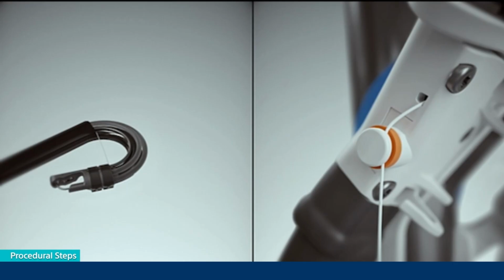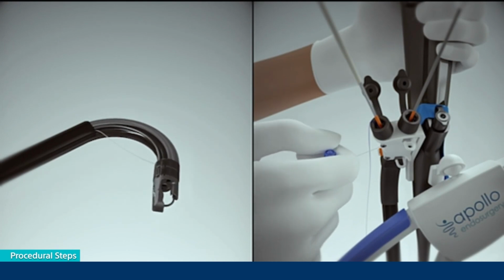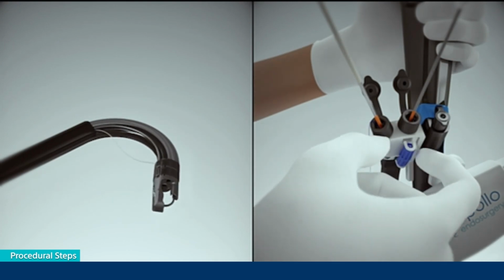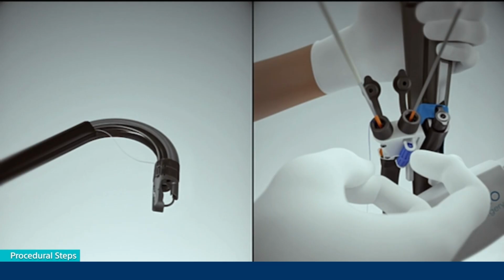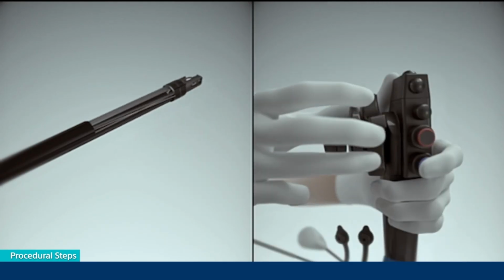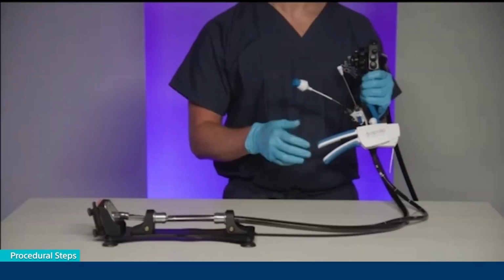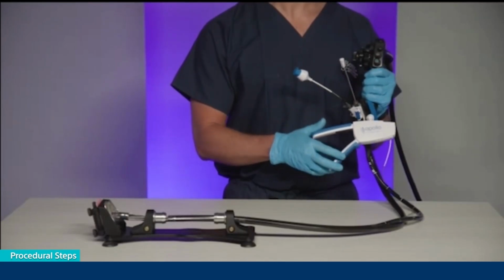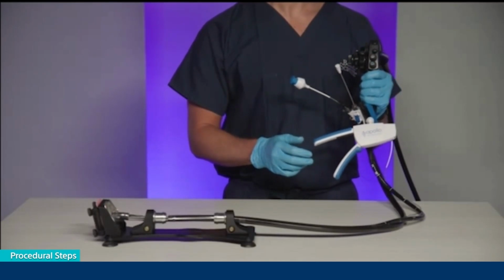Step 6. Once MaxFlex use is complete, hold endoscope up dial at its fully articulated position and then release pull string by unwrapping from brake washer and releasing the tension in the string. Do not yet release hold on endoscope's up dial. Step 7. Secure blue pull string pill on the underside of the device handle while ensuring the pull string does not wrap around handle. Step 8. You may now release the scope dial from the up position. Open our handle. Now we're in the loaded position and ready to pass our first suture.